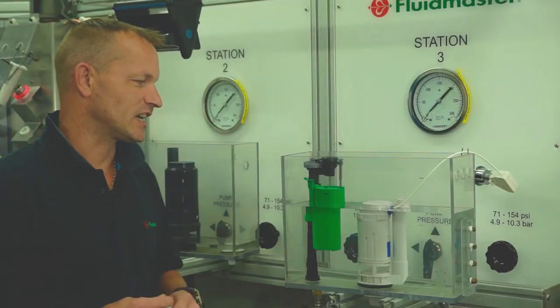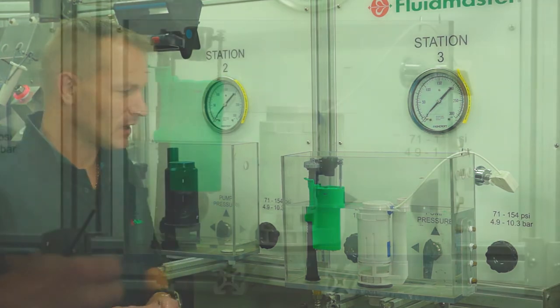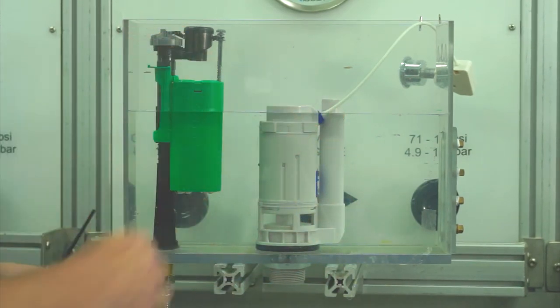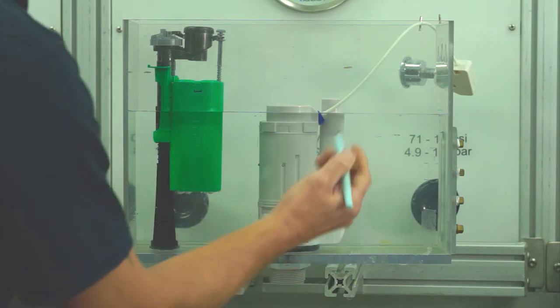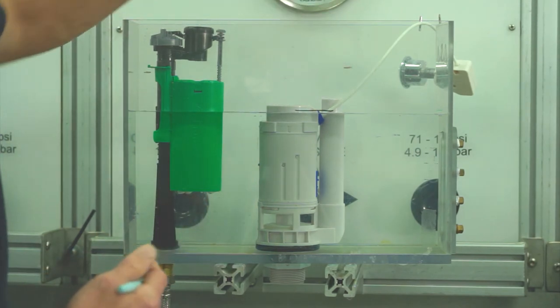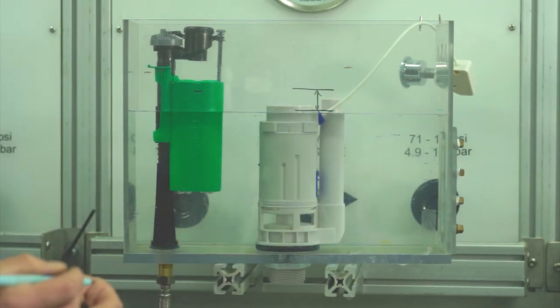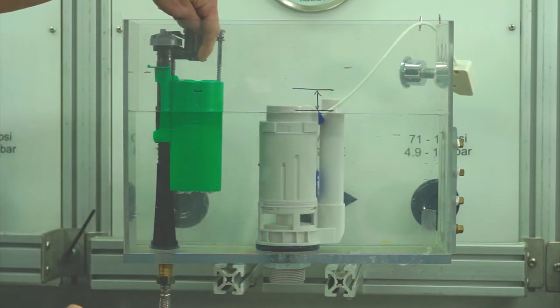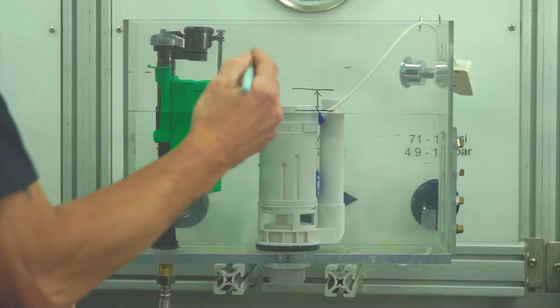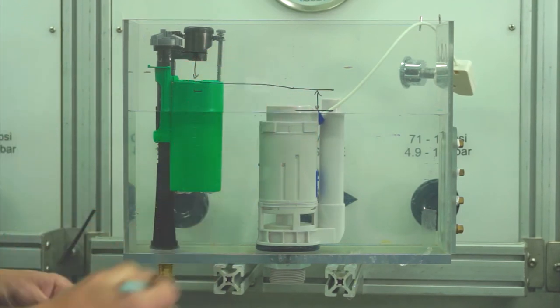With this clear demonstration tank I'm going to show you what we mean by AG and AUK1. AUK1 is an installation of the whole assembly — the flush valve, overflow and fill valve. You have your water line, we have our 19mm overflow on this valve here, which should be anywhere between 25 to 32mm above. Then we have the discharge point of our fill valve at that height. To maintain an AG air gap, the distance from the discharge point to the overflow must be a minimum of 20mm.